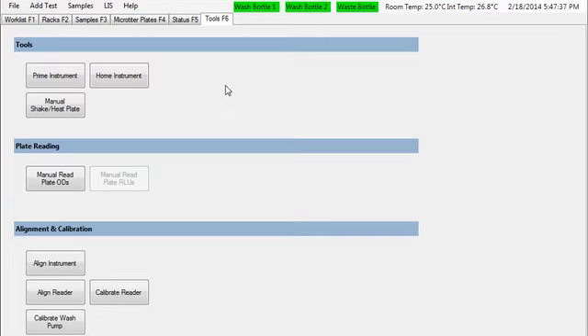The first thing you would do at the beginning of the day is prime the system with the wash buffer you're going to use. At the end of the day, you just need to prime with DI water. That's it. At the end of the week, there is an instrument alignment, a reader alignment, and just overall cleaning of the instrument that needs to be done.